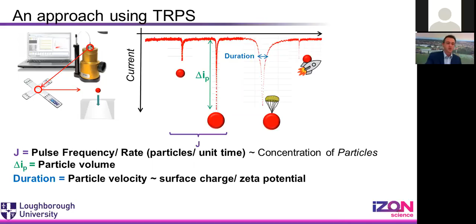In this setup though, and this is a slide that you will have seen or will be about to come across if you're about to embark on the training program through IZON, we can't simply assume, as we did in the introduction, that it's only electrophoretic mobility that we have to worry about, and that other parameters are not going to affect the particle speed. So we have our particle and it's moving through the pore. We've got the one that we're really interested in, electrophoretic mobility, because this is the thing that we can use Henry's equation on and directly relate the speed back to our zeta potential. But there are other contributing factors. We have this natural fluid flow from the head pressure, where we put our sample at the top. The fluid velocity is moving the particle from top to bottom, and if I change the amount of sample I put into the top, then that velocity will change.